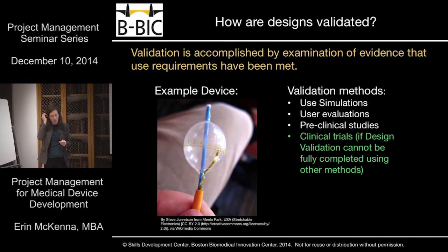I had an issue once where we had to go in and recall and redesign a product. I think when it was launched, they had brought in 4 or 5 physicians and had them deploy it into a model, and it worked fine. But when they started putting it in the hands of a wider range of physicians, they saw that some doctors were just jamming that thing in there, and the whole delivery device would collapse and make the product unusable. So you want to bring in a range of users to make sure that they can do what you need them to do, and can use it without breaking it or creating other unexpected or undesirable issues.